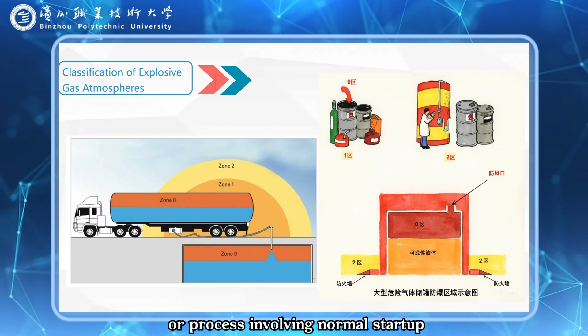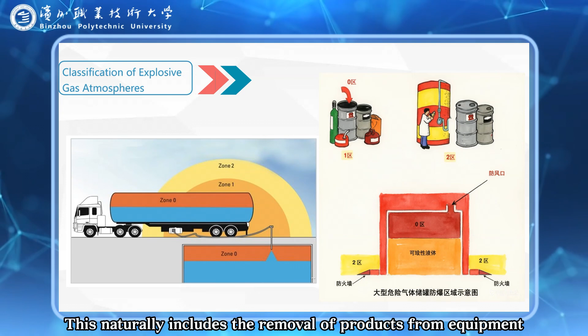Zone 2 refers to an environment where explosive gas mixtures are unlikely to occur during normal operation or where they occur only for short periods. Normal operation refers to a working state or process involving normal startup, running operation, and shutdown. This naturally includes the removal of products from equipment as well as normal operations, such as opening and closing equipment, handling lids, feeding materials, removing impurities, and operating safety valves and drain valves.